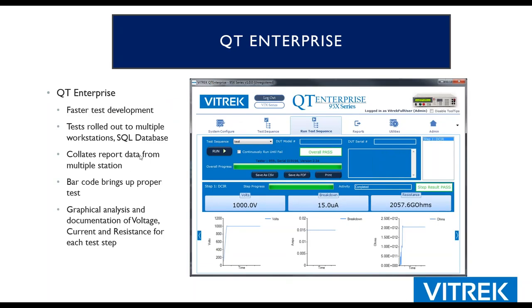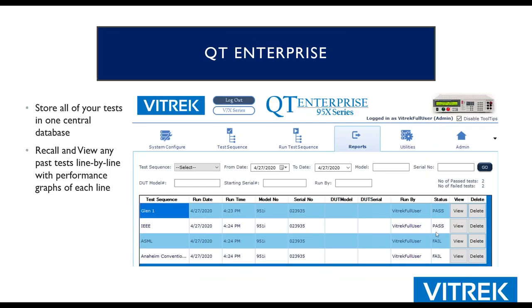So this resides on an SQL database. You can use it across multiple different stations, even in multiple locations. And what it allows you to do is pull a test sequence, load it into the tester, load it on the computer. This can be pulled from the barcode or serial number of the unit, run the test, save the report, and actually have some traceability so that if there was an issue even 5 years down the road, you can go, yeah, serial number 123, we tested it on this date, and we used this tester, and that was the time, and that was the user. And you really have all the information right there in front of you, and it's accessible.